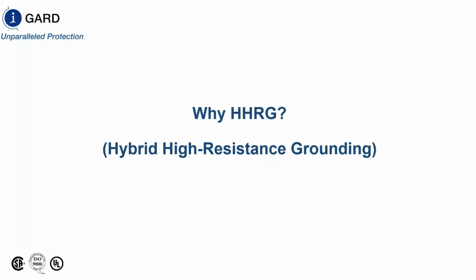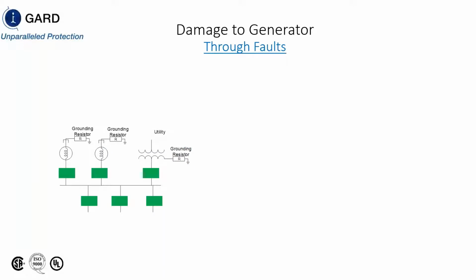And this all started because there were some catastrophic failures in the United States, specifically the Pacific Northwest, where they've had some generators fail drastically under a stator fault winding, and so the hybrid high resistance grounding system was developed for that. So we're going to take a look.